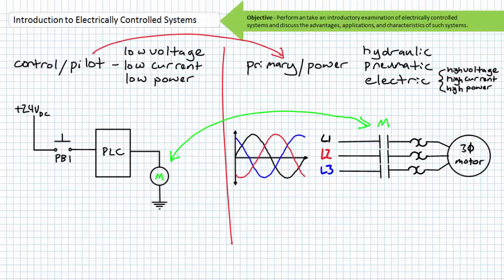In its de-energized state, the contactor is in its open condition. When the coil of the contactor is energized by the low-voltage pilot signal, the contactor closes the electrically isolated primary electrical power switches. There is a very clear distinction between the different flavors and magnitudes of pilot and primary electricity, despite their superficially similar labels.